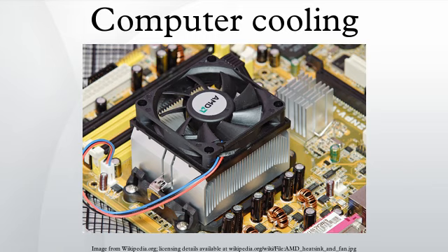Heat dissipation of over 1000 watts per square centimeter has been reported. The system can be operated at lower pressure in comparison to the microchannel method. The heat transfer can be further increased using two-phase flow cooling and by integrating return flow channels. Phase change cooling. Phase change cooling is an extremely effective way to cool a processor.